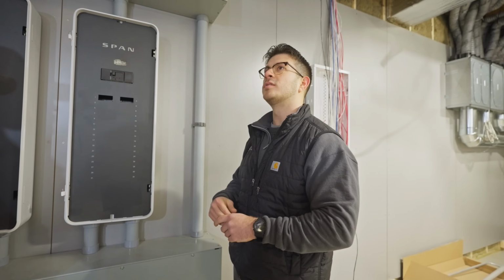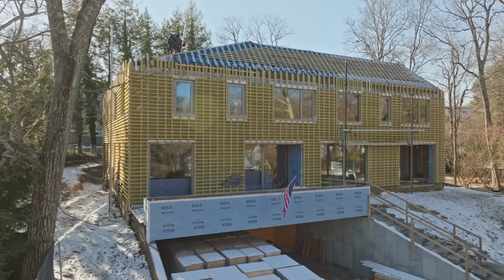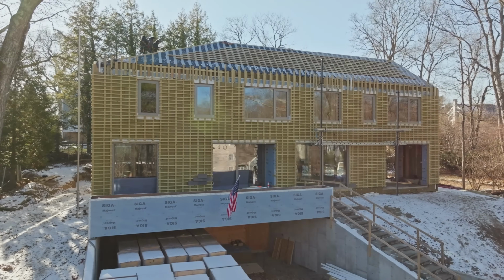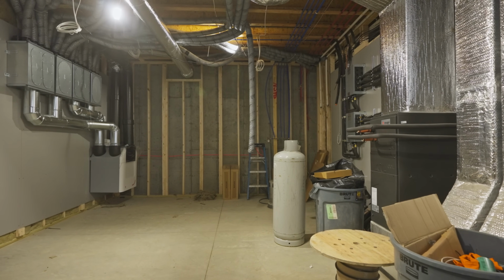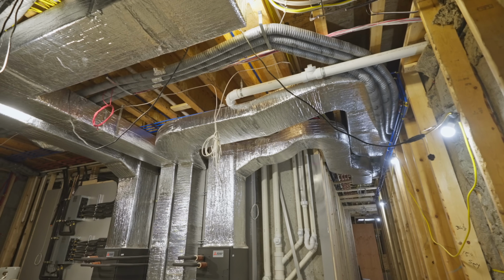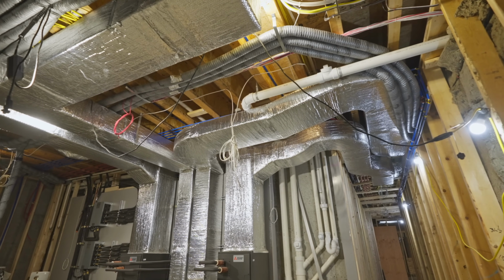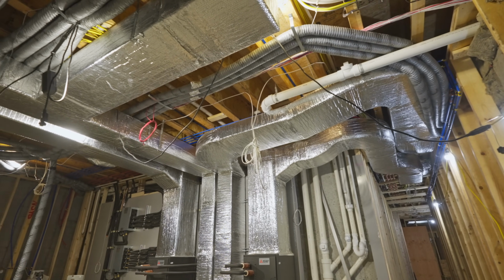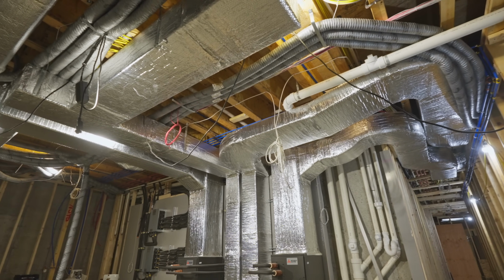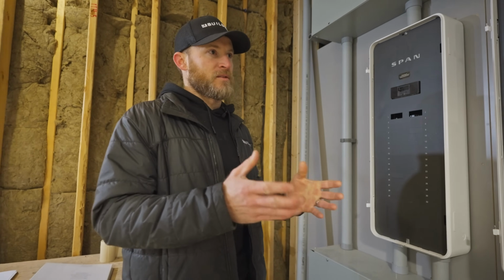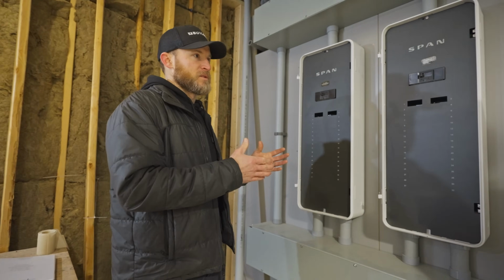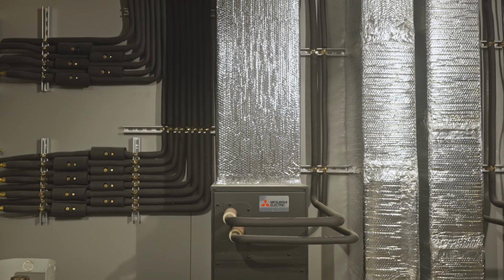Obviously 400 amp was sized right for this property. It's a big house, so with a 400 amp service it seems a little small, but that's because everything in here is so high efficiency. When we were sizing the heating and cooling equipment, we had a massive cooling load, and we were able to reduce that by 50% with a couple of decisions. We'll talk about that in a future episode, but it's a big reason we're able to stay within that 400 amp. It's important to go through that exercise.